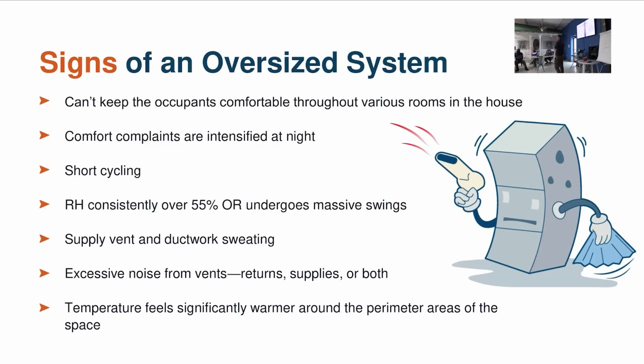So what I'm going to encourage you to do is, first of all, right sizing. Make sure that you're not oversizing equipment. A lot of times, if you can deal with the envelope, the attic, the insulation, and some other things, you may be able to go down a little bit in size. And if you can, that's a win for multiple reasons. Because now the ductwork that was kind of sketchy actually is good, right, because you're trying to push less air through it. Now where you may have had shorter run times and short cycling, you may be getting longer run times. So downsizing equipment, right sizing equipment, is a really key point to getting better efficiency out of the equipment, getting better capacity consistently, meaning you're actually providing what you told the client you would get.